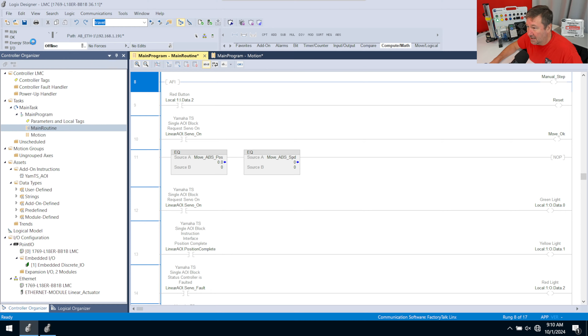Now, by default, only the main routine, or the one with the 1 here, that's all that's going to be executed. So if you want this motion routine to execute, then you're going to have to tell it here to go do that. The easy way to do that is just highlight the rung and type J, S, R, and press the enter key. That inserts the rung and the instruction, and then we can go and find motion. But all right, in that case, you do need to know what all of them are.